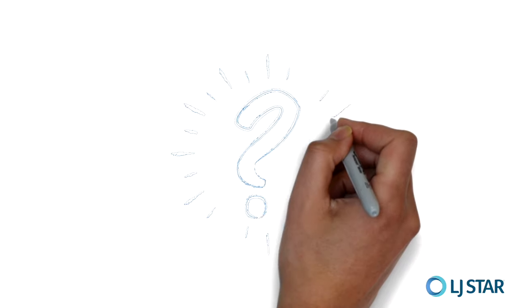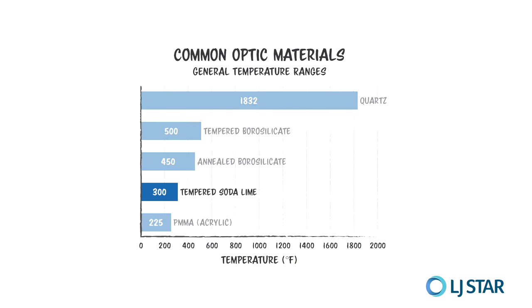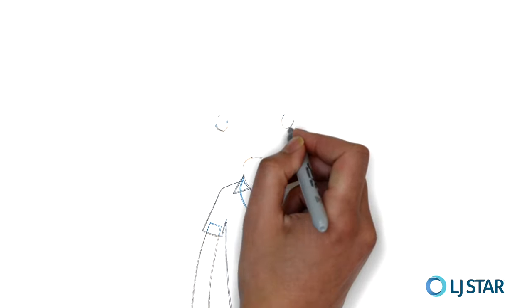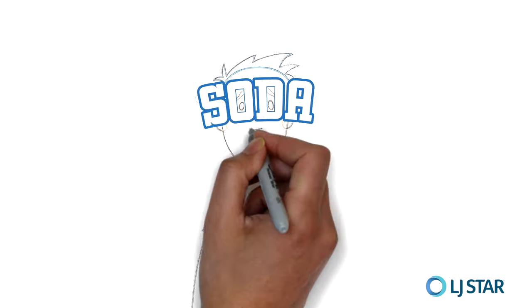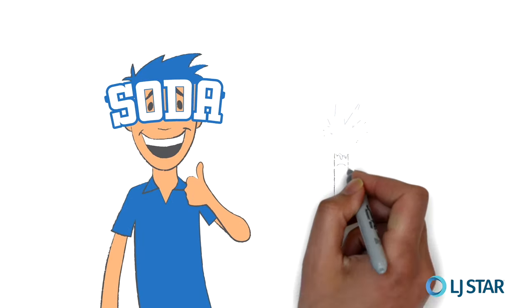Let's examine the engineering properties. First, let's understand how high temperature affects glass. At temperatures less than 300 degrees Fahrenheit — typical for a non-critical application — standard soda lime glass may be used. If your application has higher temperatures up to 500 degrees Fahrenheit, you need to be sure you're using only certified borosilicate glass, not pseudo-boro imitations that are actually just soda lime masquerading behind a boro brand name.